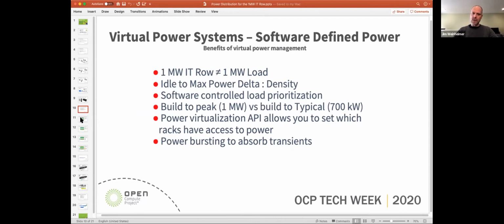So let's assume for the worst case scenario that the difference in percentage between the idle power load and the max power load is the same for your 10 kilowatt racks as it is for the 100 kilowatt racks in the 1 megawatt row. If we apply the same deratings to the 1 megawatt row as most of us have experienced in data center facilities planning, the actual draw of a 1 megawatt row will be somewhere in the 700 kilowatt range. That uncertainty about the real world loads leads us to overbuild the electrical systems and to strand capacity, which means we're building for the worst case and not the average loads.